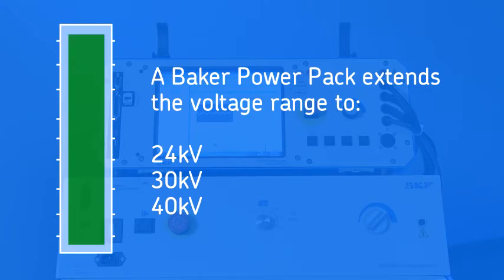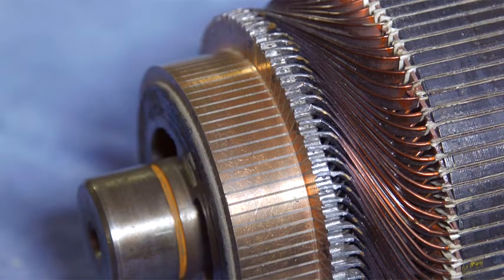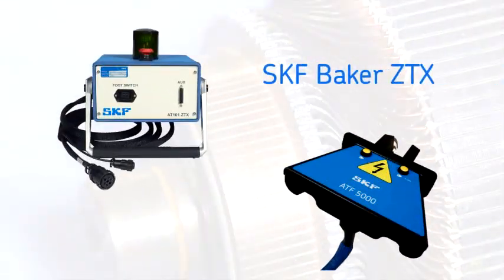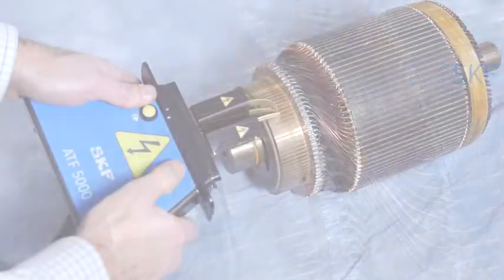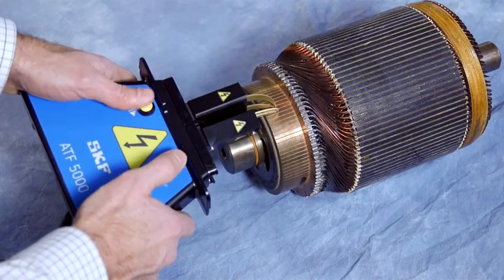DC motor armatures can also be tested using an SKF Baker ZTX adapter with an SKF static motor analyzer. The ZTX lowers the surge voltage while increasing the current. This allows bar-to-bar testing of the armature with excellent fault location.